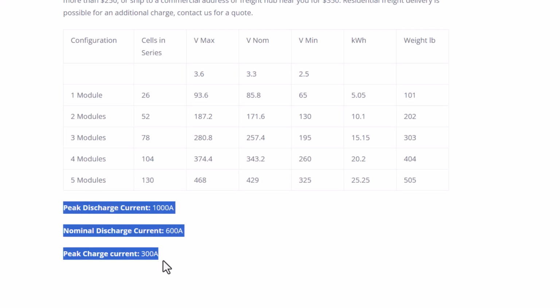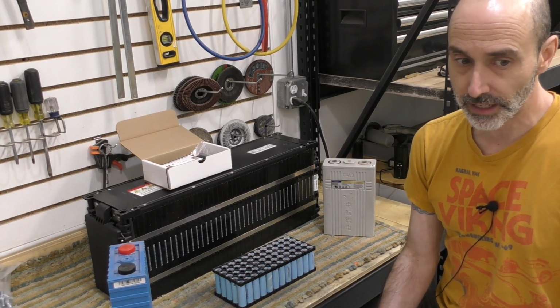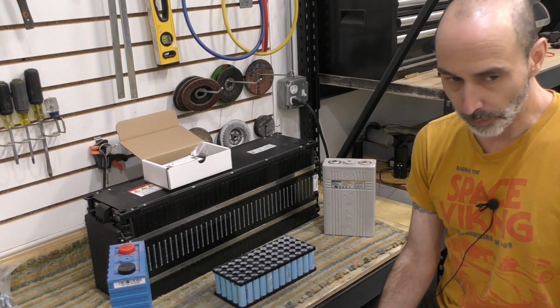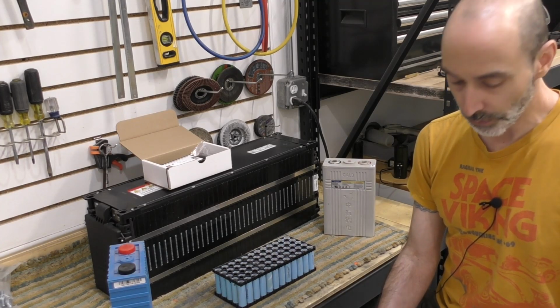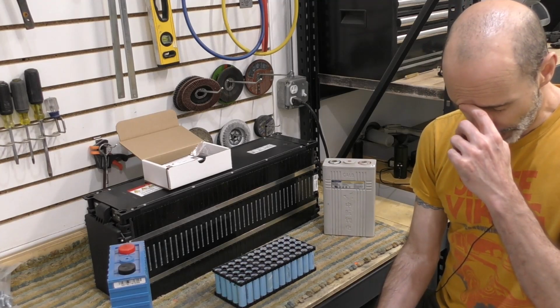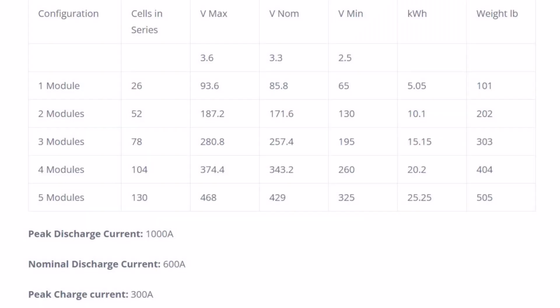Peak discharge current: 1,000 amps. Nominal discharge current: 600 amps. Peak charge current: 300 amps. They use a little different language than some other vendors, but my guess is peak discharge current is probably the 10 second rating, and nominal is probably the continuous rating. But look at that - per module, on a 60 amp hour module, that's a 10C continuous discharge rating.